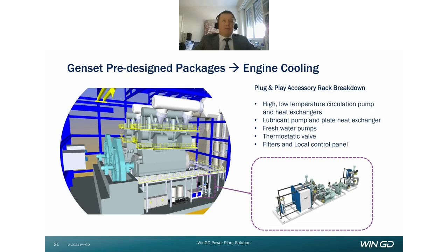On the same skid, we can find the lubricant pump and the plate heat exchanger to cool the engine lube oil. A set of pressure and temperature sensors are also foreseen in the design to monitor and control the engine fluid cooling loop. A single electric point of connection is also implemented by means of a local control panel mounted along the skid to connect the accessory rack to the plant power and control network. The accessory rack dimension and weight enable its transportation by means of a standard 40-foot high cube container, reducing the overall logistic cost.